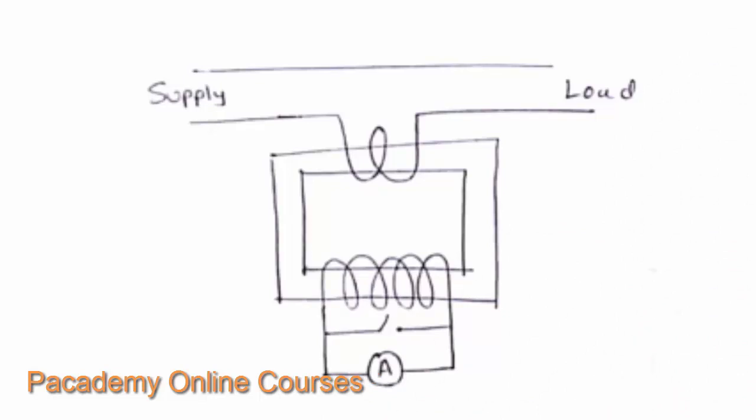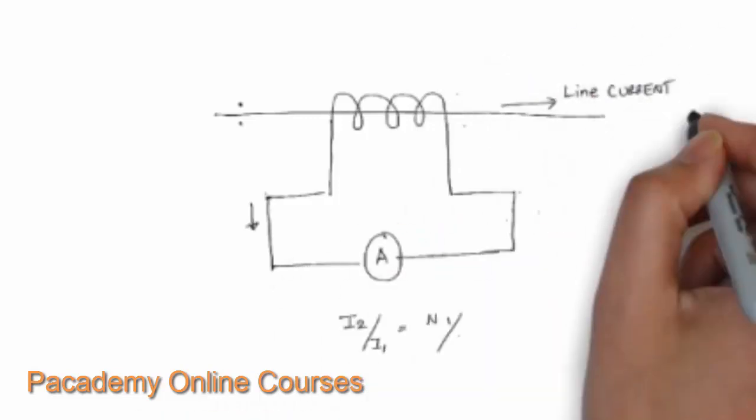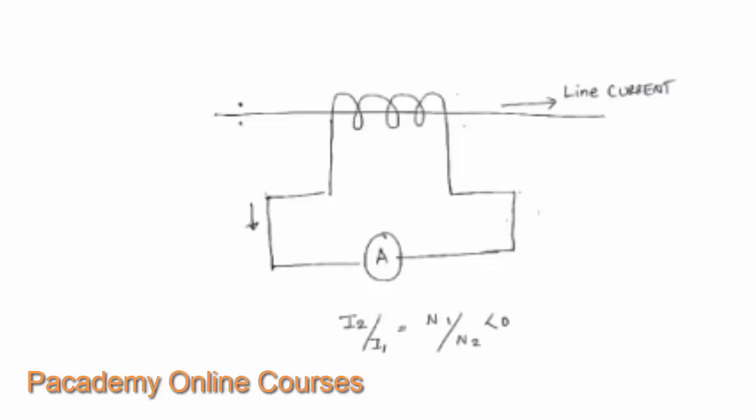Looking at the diagram of a current transformer, it is connected in series with the supply line on which the current is to be measured. The primary has a few thick turns and the secondary has many turns. The current is stepped down in the secondary and can be easily measured by the ammeter, which is calibrated to output the current considering the transformation ratio. In the simplified diagram, I2 by I1 equals N1 by N2, which is less than 1.